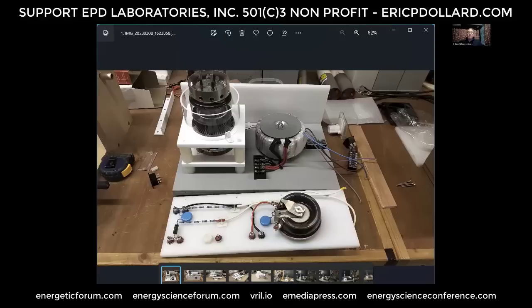It does require quite a lot of infrastructure. It has about a 350 VA heater requirement just for a single tube, so there you can see the big toroidal transformer. That's also a 240/120 volt transformer, because in the UK I'm going to run it off 240, and in America off 120. I know Aaron has 220 in the shop as well, which is good. You can also see at the bottom there you're starting to get some of the high voltage bias.